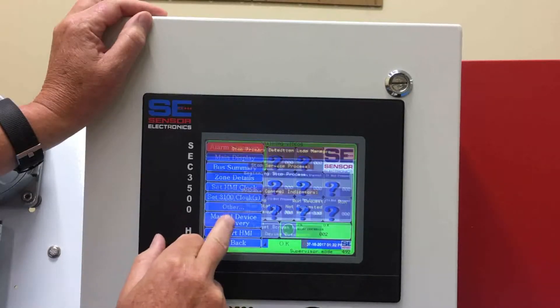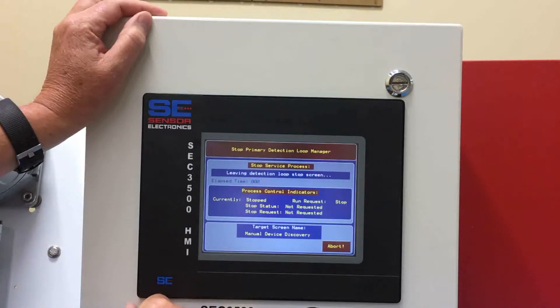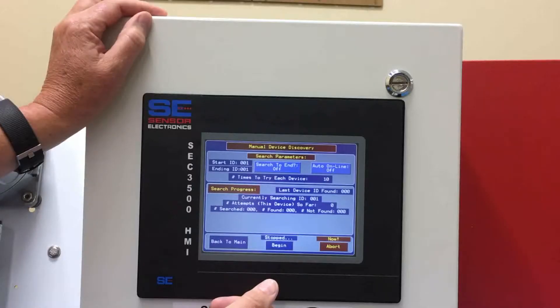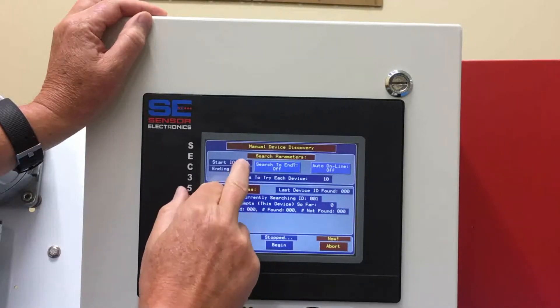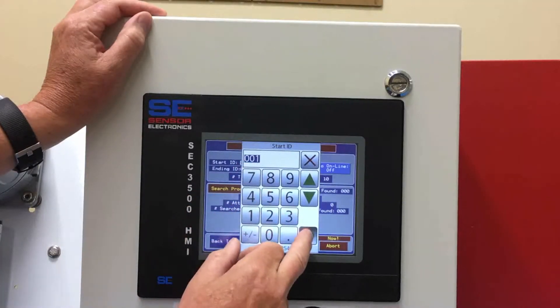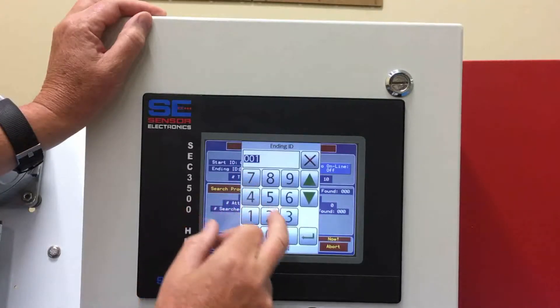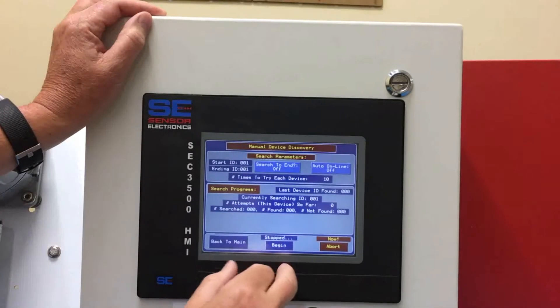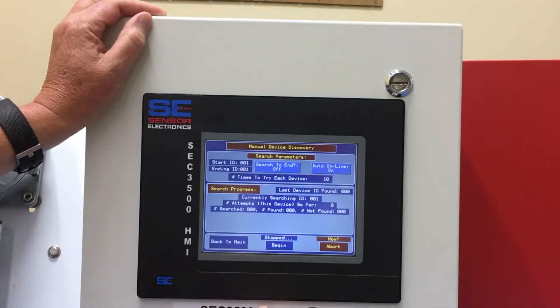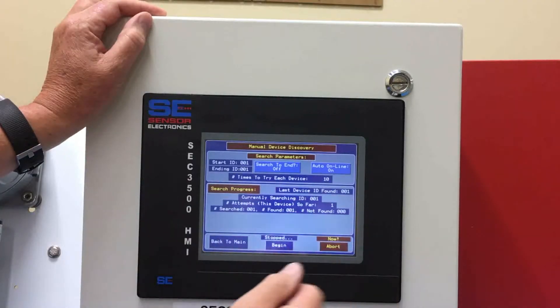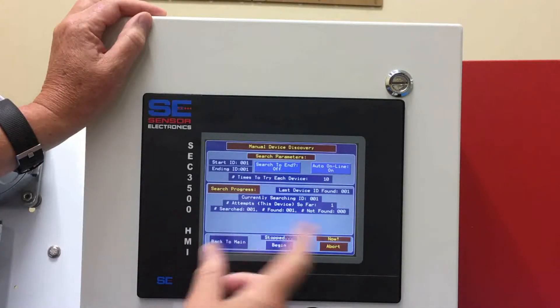We don't have anything in other, but we do have the manual discovery device. This is where you go on a new system, or if you're going to add detectors to an existing system — you punch in the ID number you want to start with to search, then the ending ID if you want to search a group of numbers. Then you select auto online, which will automatically bring it online and search for the detectors.